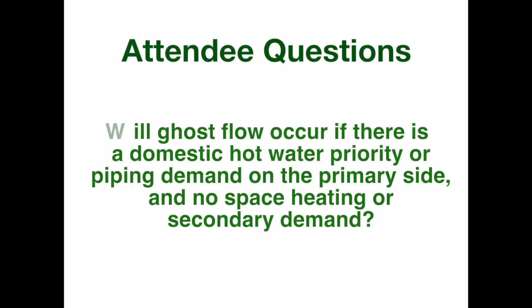Okay. Nice job, Mark. I do have a few questions here. Mark, will ghost flow occur if there is a domestic hot water, a DHW priority or piping demand on the primary side, but no space heating demand, or I guess no secondary demand? So can you get ghost flow occurring across a hydraulic separator in that case?